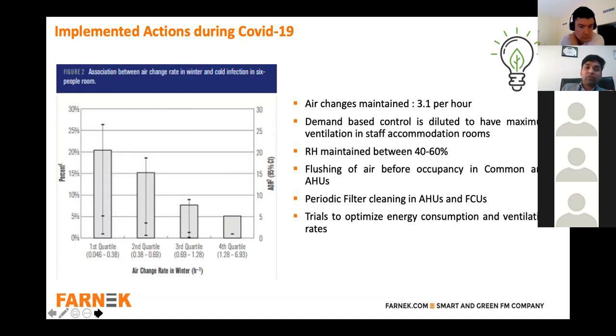In addition, we try to maintain room humidity levels between 40% and 60%, where virus spread is minimum, as per CDC guidelines. Periodic filter cleaning is done to improve filtration effectiveness in AHUs and FCUs for better indoor environmental conditions. We also do flushing of air before the occupied period in common area AHUs. The flushing time is decided based on various trials conducted with the systems, observing the deterioration of contamination. We conducted an enormous amount of studies for individual systems and adjusted the flushing time accordingly.